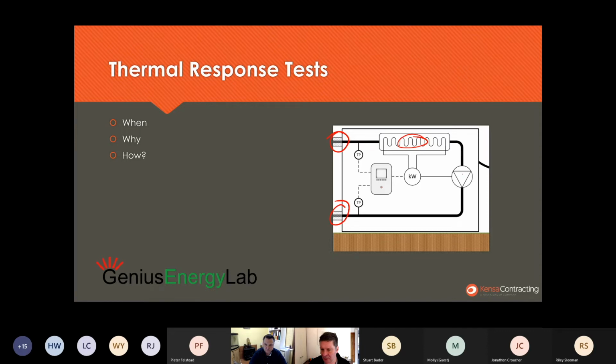We've got a pump here, which drives the fluid round the loop. We've got a power supply, which is delivering power to both the electric boiler and the pump. And hopefully all the energy that's going into that electric boiler, plus all the electrical energy that's driving the pump, ultimately ends up as heat in the loop here. And so we measure that with an electrical meter.